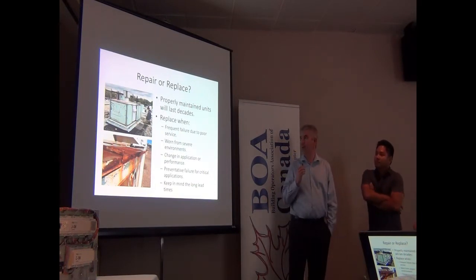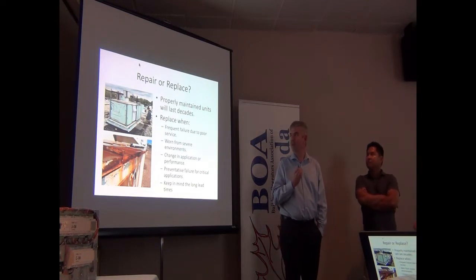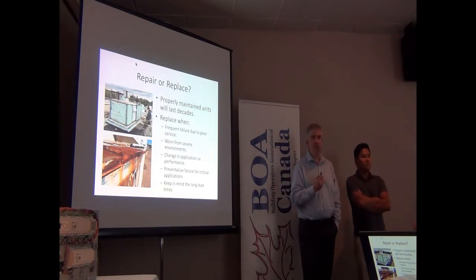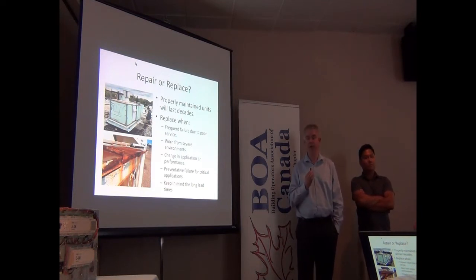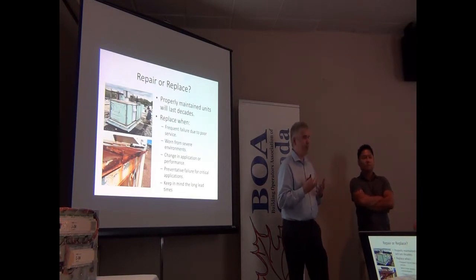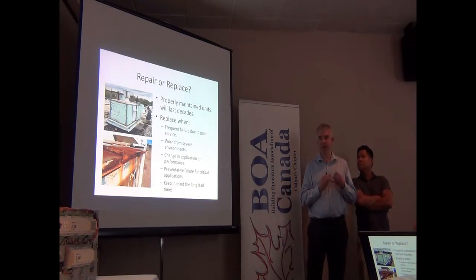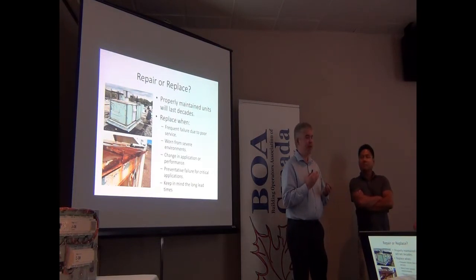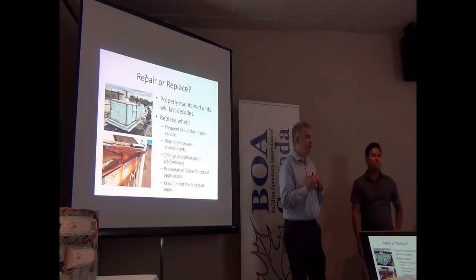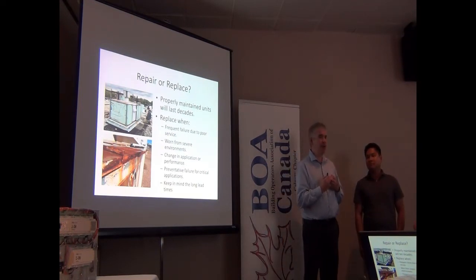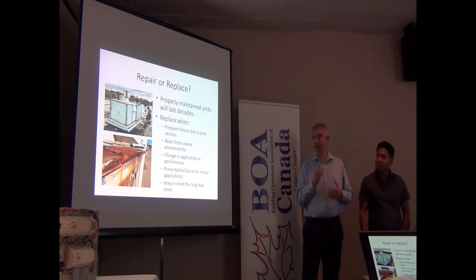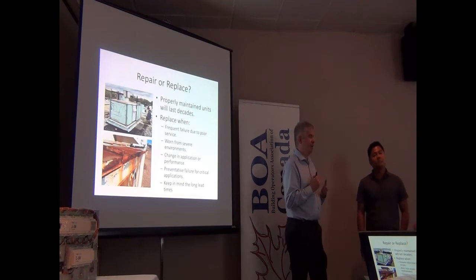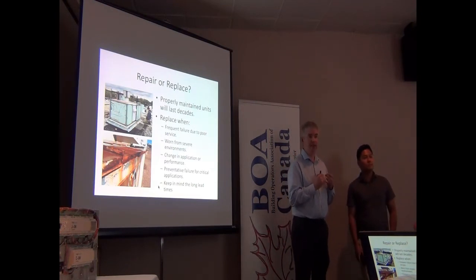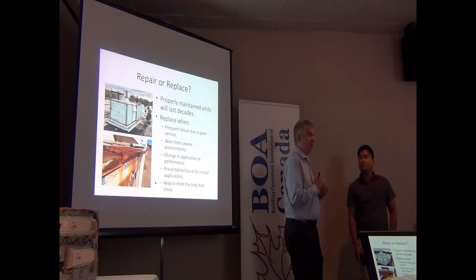Okay, so we're going to talk generally about replacement. The first thing to think about for replacement or repair is, what is the lifetime of an air handling unit in the first place? We can think about what type of unit you have, because that can be a huge factor. If you take an air handler that just has a couple of hydronic coils in it, heating coils, cooling coils, no gas fired section, nothing else that's really specific to it, that unit could last you decades, because the actual components in it, aside from bearings, that type of thing, don't wear out particularly fast.